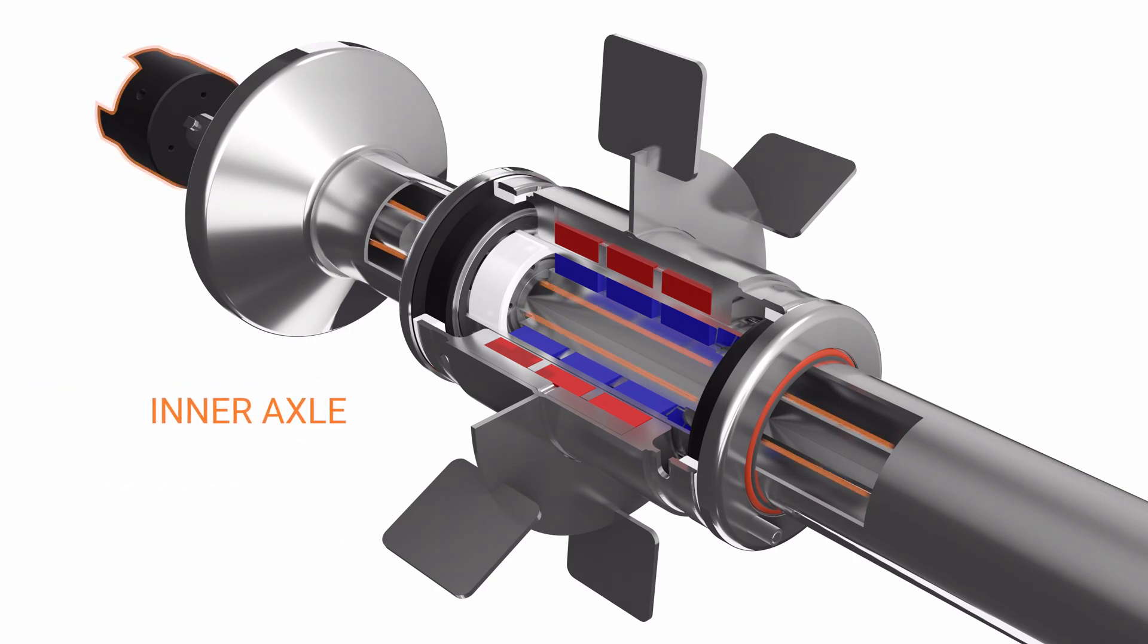The mixer consists of an inner axle which rotates during agitation. The axle is mounted in a hermetic cylindrical housing which remains stationary and separates the reaction medium from the external environment. The drive magnets are affixed to the inner axle.